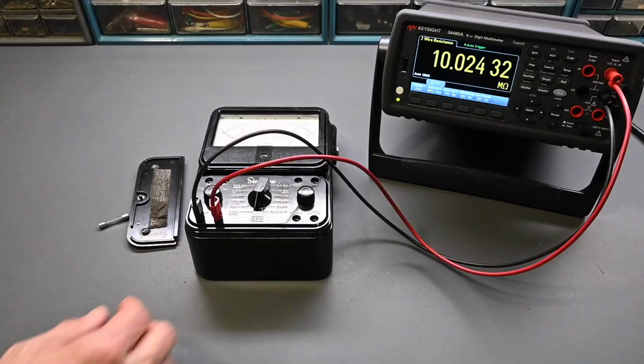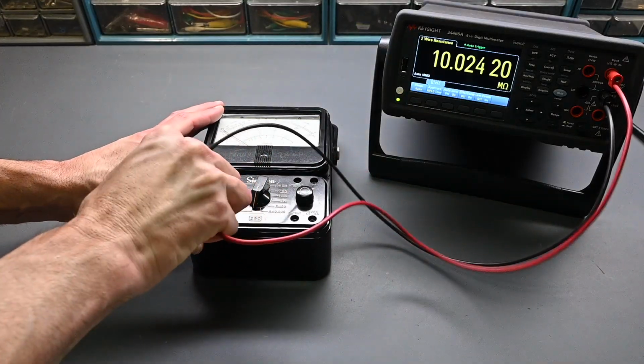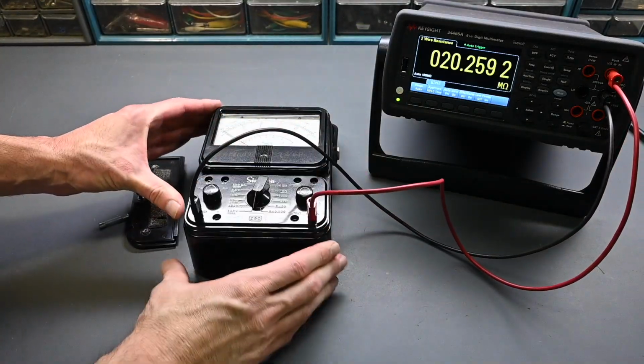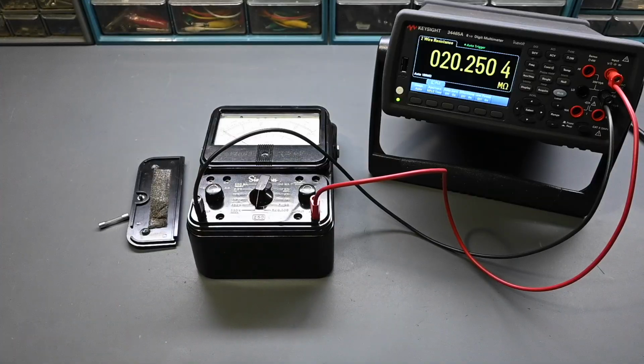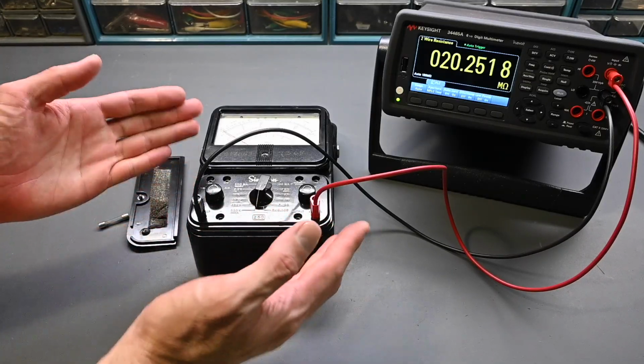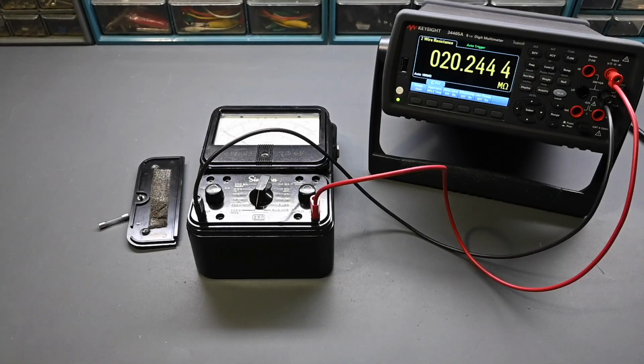And then what I need to do is move this over here to the 1000 volt jack. So that should be 20 megohms, and it's a little bit on the high side. So yeah, the numbers are off a little bit, not really where they should be. No surprise that if you were to take an actual voltage measurement, it really wouldn't be all that accurate.